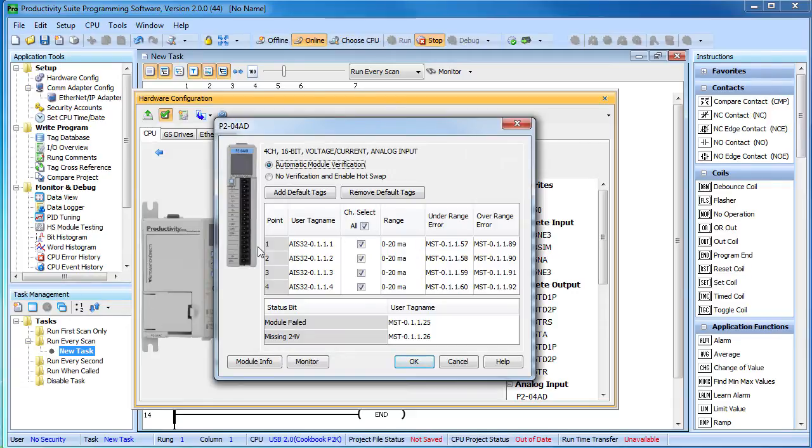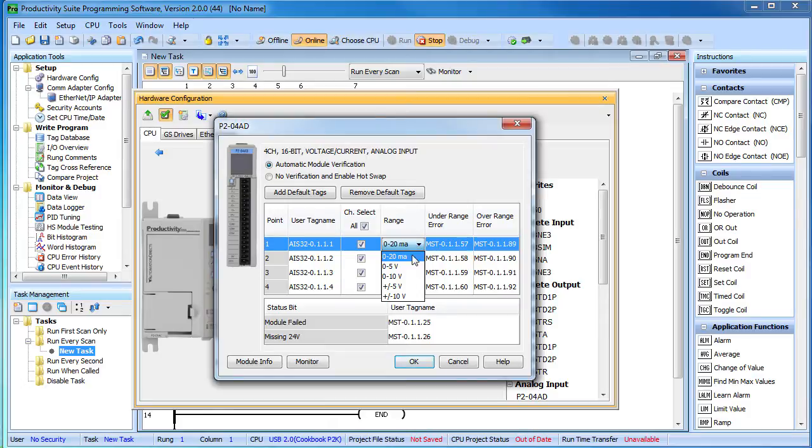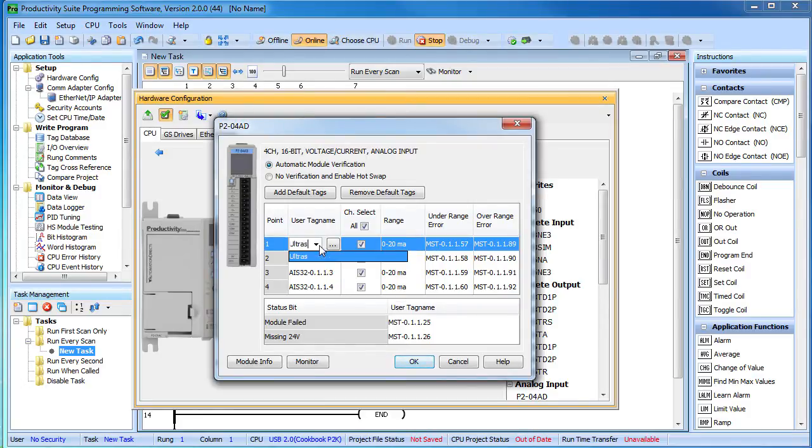Let's double click on the analog input module to set it up. Channel 1 is the ultrasonic sensor which has the current output, so we select the 0 to 20 milliamps and let's change the name to ultrasonic.